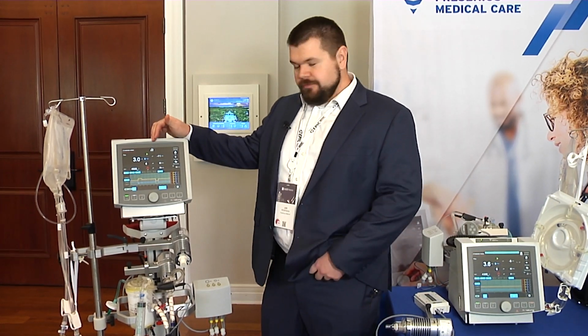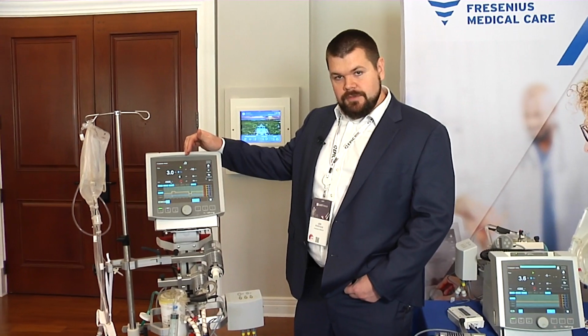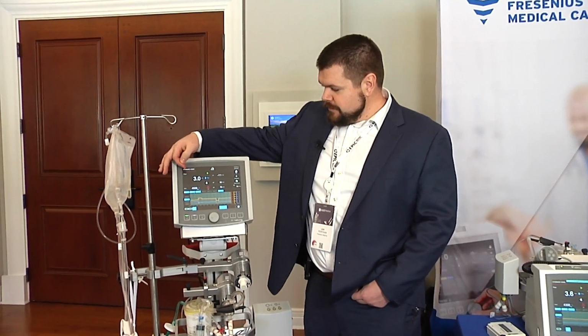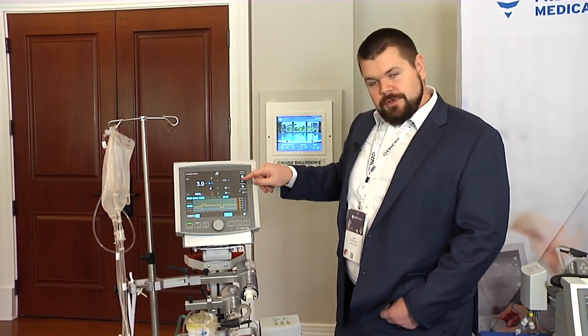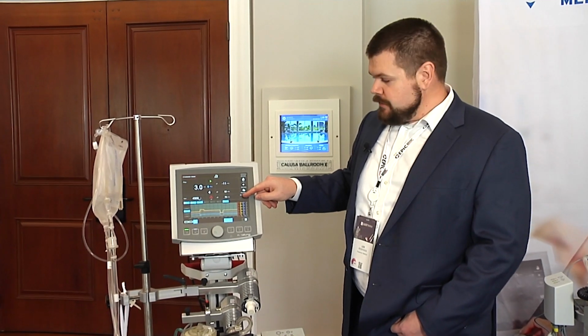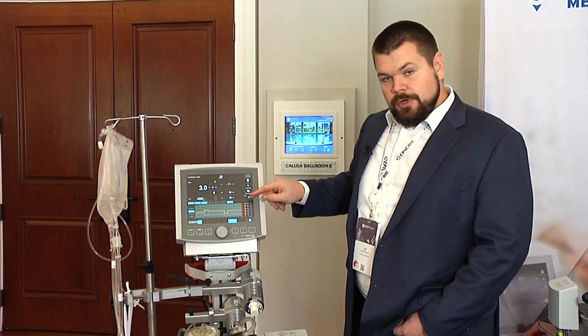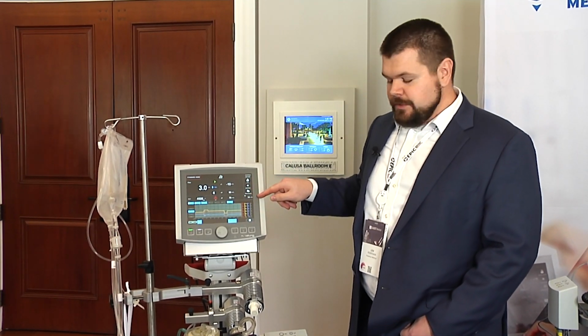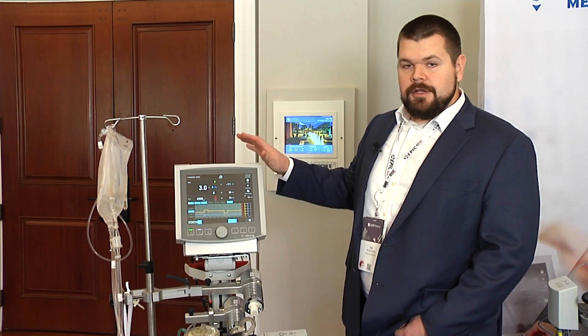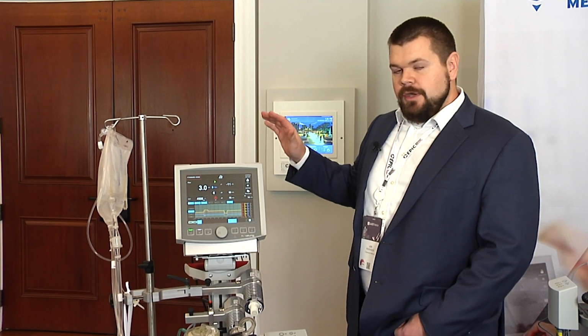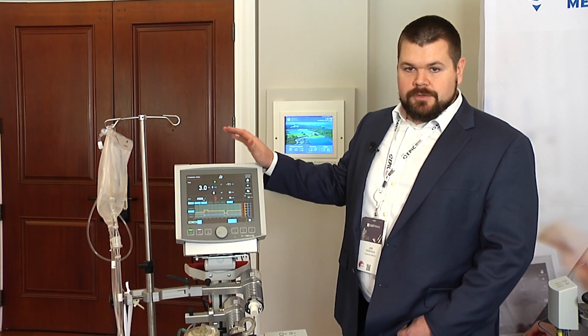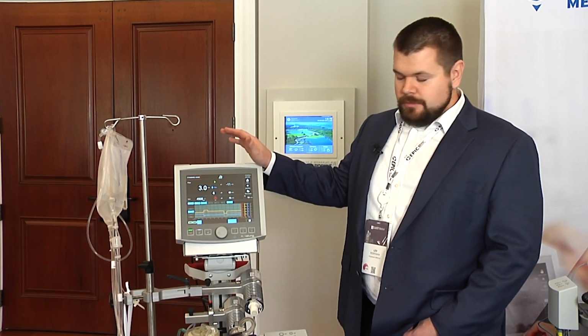If you start off looking at the screen here, you'll see that the data that you get from this machine includes the flow, speed, and then 3 non-invasive pressures. So you have negative venous, pre-membrane, post, and then a calculated delta P. All of these pressures are non-invasive and self-calibrating, so they don't require any work for you to maintain, and they allow you to have some insight into what's going on in your circuit and be proactive in your troubleshooting.